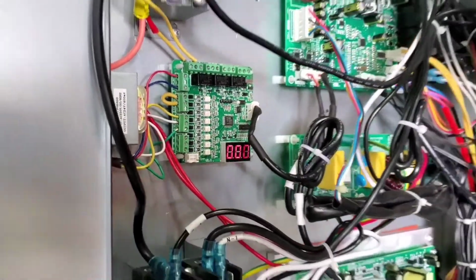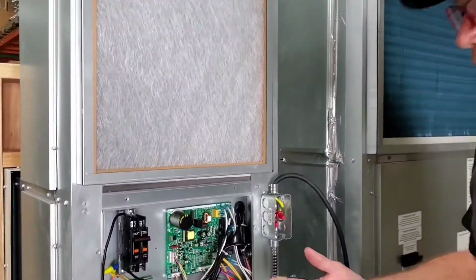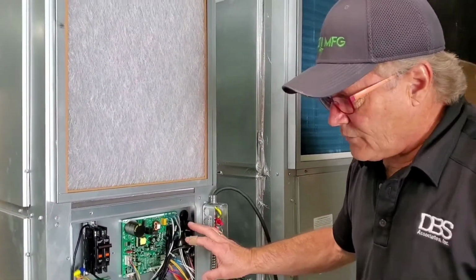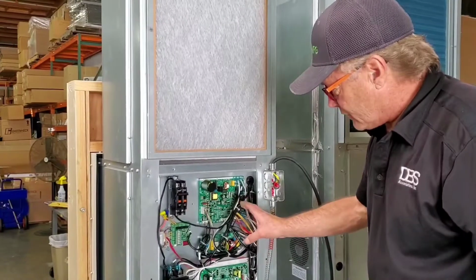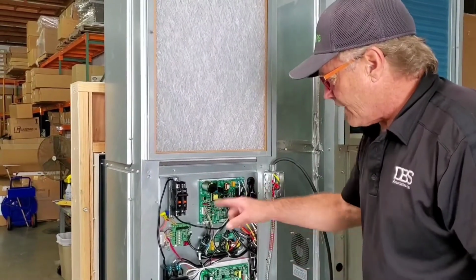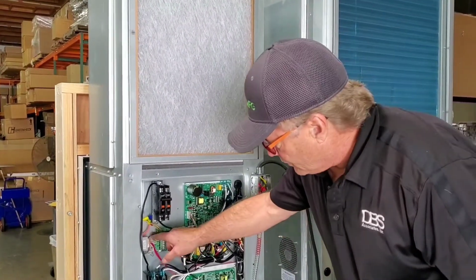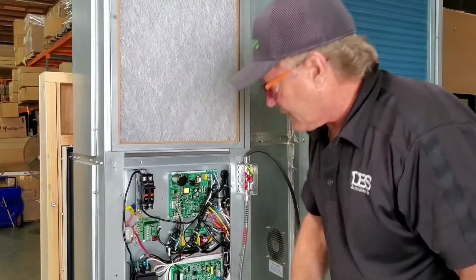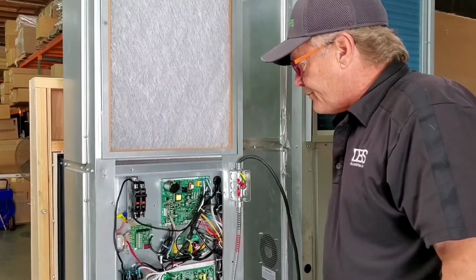That's all you need. This unit does not require 3-speed fans because it's all done through the modulation of the compressor with the fans here. So you just need one fan wire. And that common can be alleviated. You don't have to have a common if you have batteries in your thermostat, but we have it here on this one to show you.